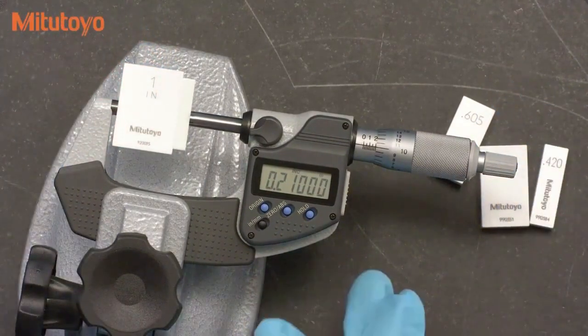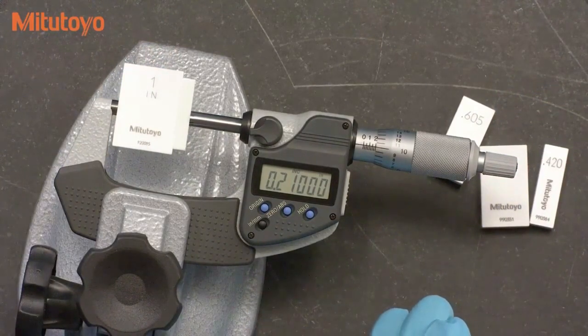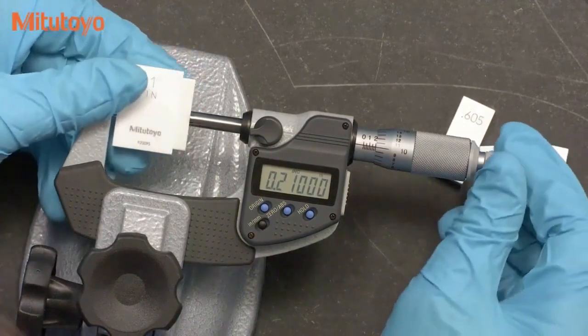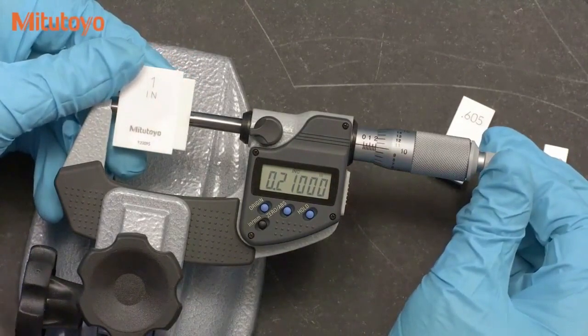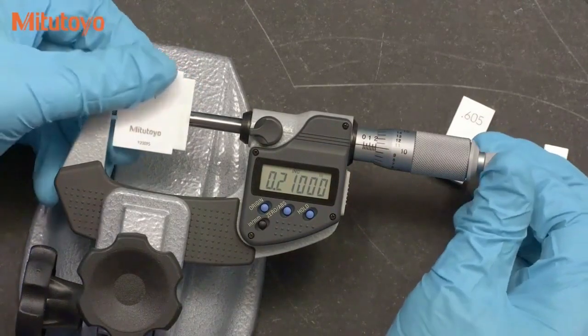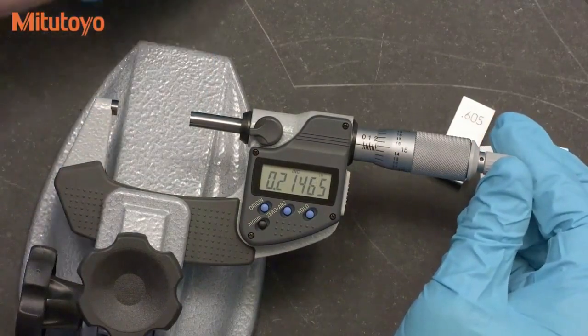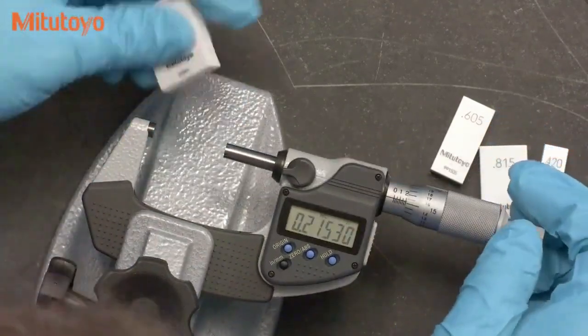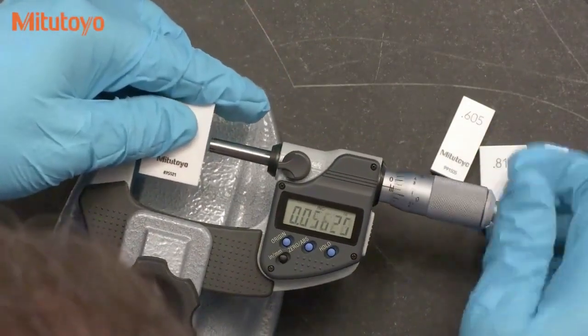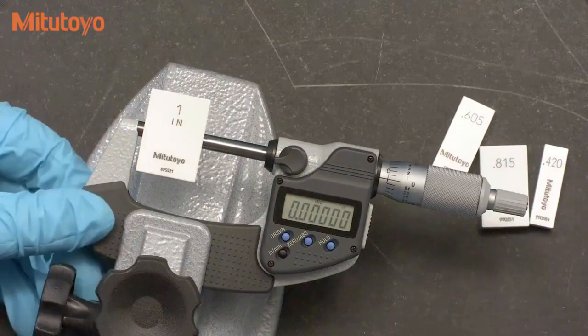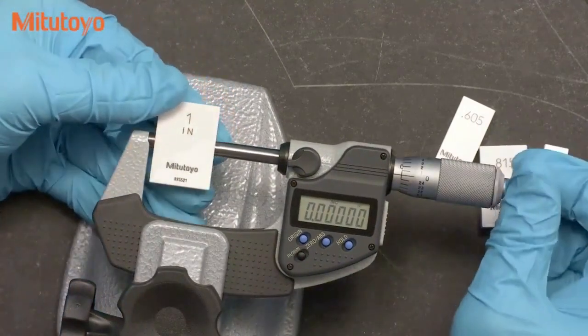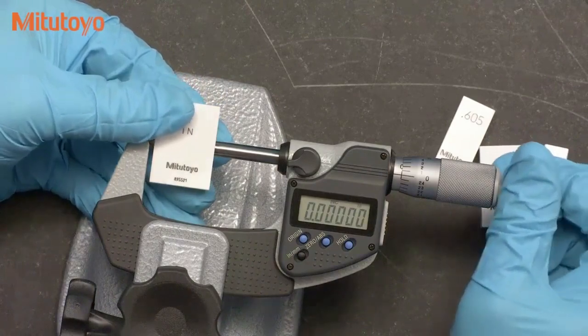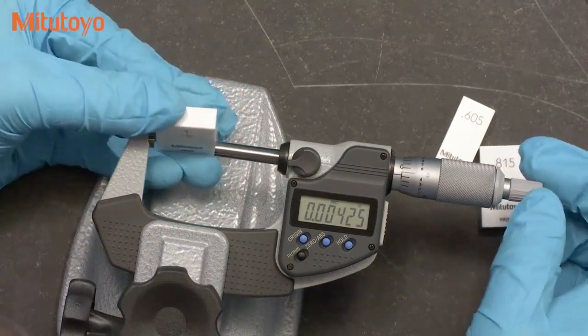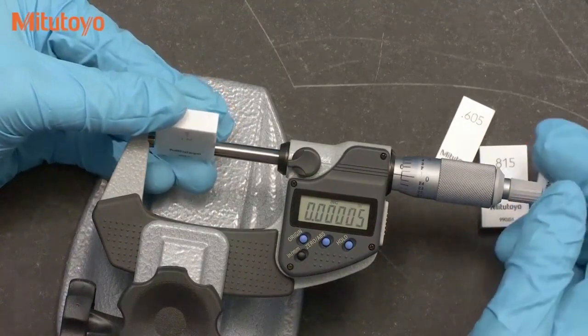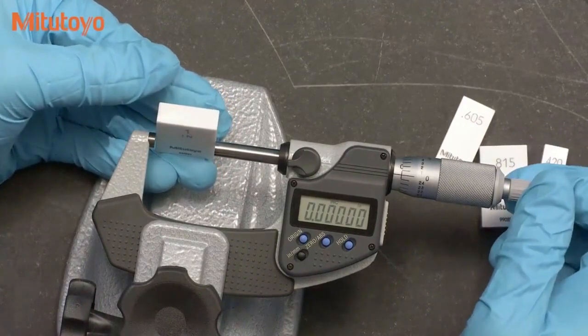You would then continue with the other 4 blocks to complete the test. For the parallelism of a larger micrometer, the B89.1.13 standard recommends a test similar to the small ball, but instead uses the edge of a gauge block. My 0 is already set with this gauge block. Now what I'm going to do is move the gauge block up, down, in, and out to look for variation. And I'm going to measure right at the edges, like that.